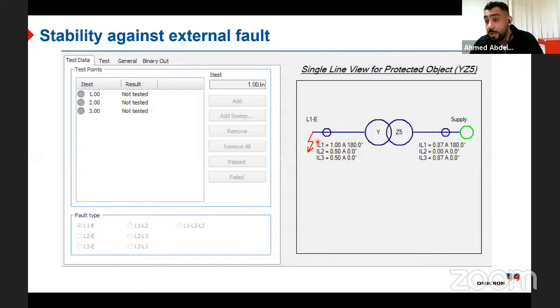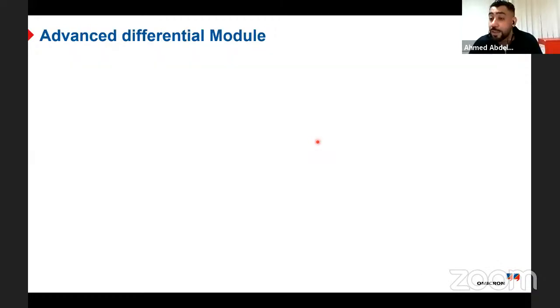What else can I do? I can test the differential configuration beside the slope. I need to confirm that if I put a slope of 0.3 and 0.7, I understand or find that my system is really working on this slope, 0.3 and 0.7. What is the solution I have? I have the advanced differential module.